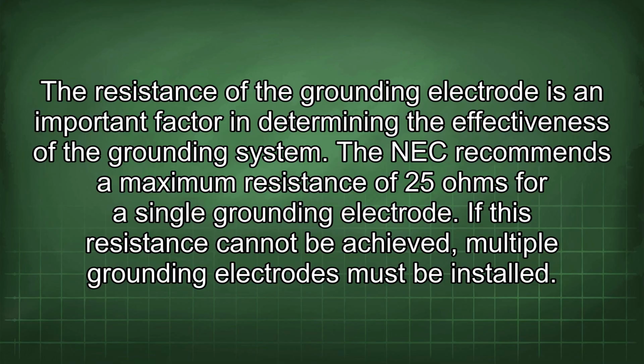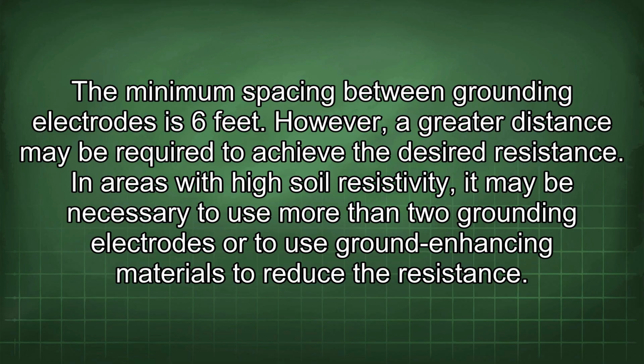If this resistance cannot be achieved, multiple grounding electrodes must be installed. The minimum spacing between grounding electrodes is 6 feet. However, a greater distance may be required to achieve the desired resistance. In areas with high soil resistivity, it may be necessary to use more than 2 grounding electrodes, or to use ground-enhancing materials to reduce the resistance.